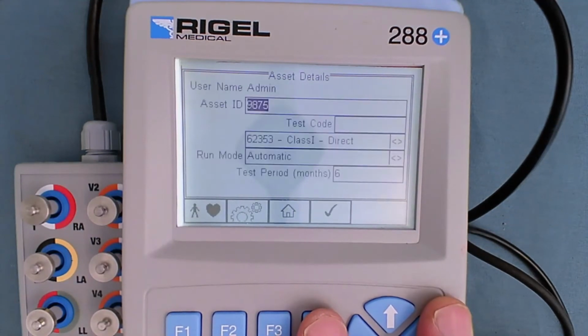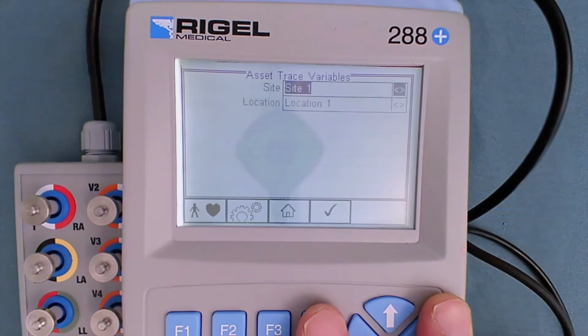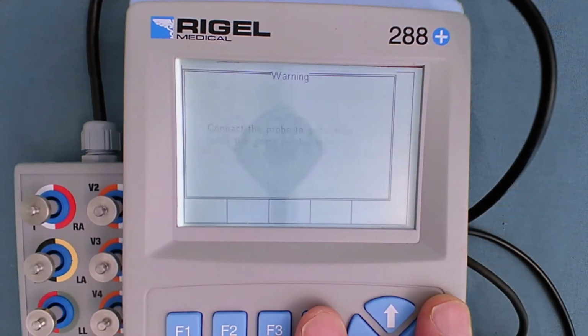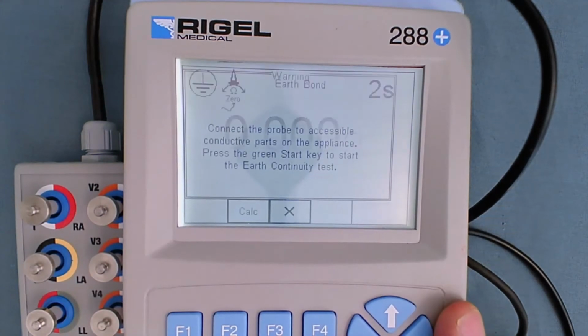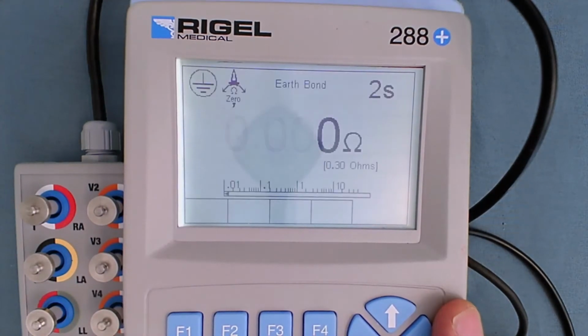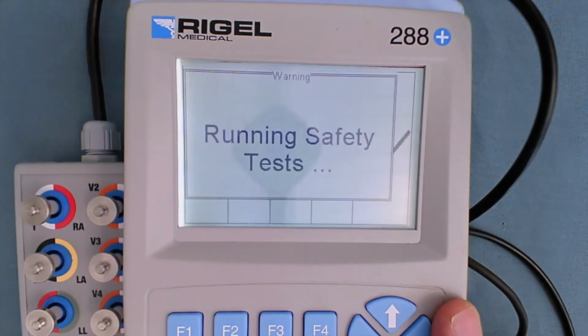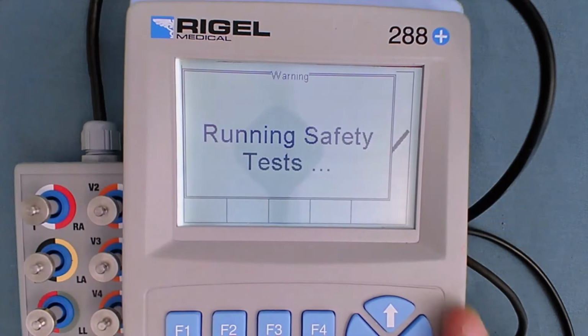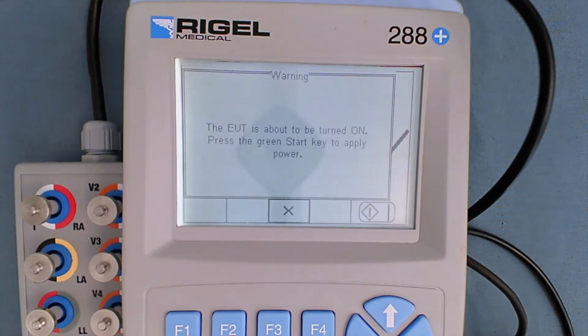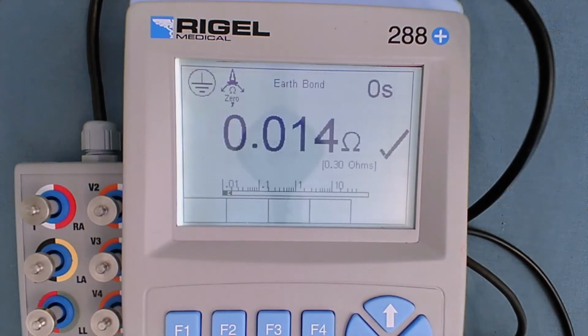Okay, so we just press F4, go through the system, and that will perform an automatic safety test once you've got your applied parts configured and your test lead onto the exposed conductors. We haven't actually got any test leads connected, so applied parts is just to show you how to configure an automatic test. As you can see, it's very intuitive, quick to run. I will give a demonstration quick shortly with some of the leads connected.